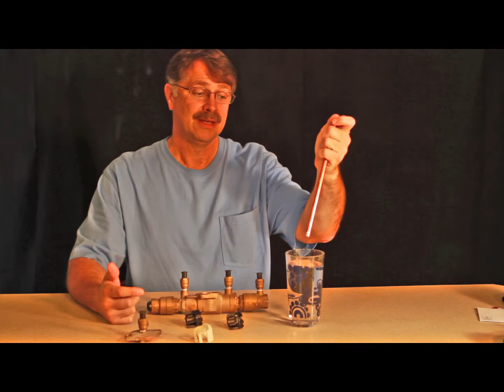So you lose water pressure out at the street, and the open sprinkler head is right here. It creates suction and could theoretically pull the grub control or whatever back into the system, into your house, out to the street, and then when everything gets repressurized again, you could have water come back up in your house, your next door neighbor's house, the house across the street. So that's what we're trying to prevent. This thing makes sure that cannot happen, because these two guys right here both shut down in the event of that kind of a situation.